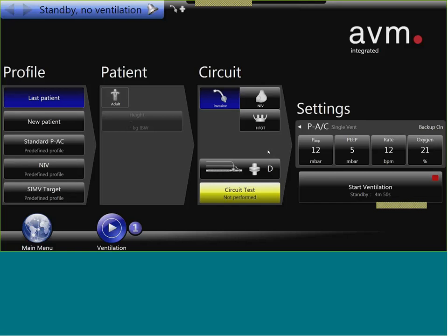Because it's for HFOT, it's on purpose. We just want that there is no mix-up between oxygen therapy and non-invasive and invasive. There are other competitors out there which have HFOT in the same panel as any other ventilation mode, and we just thought there is no alarming at all. So if someone is starting the ventilation and unfortunately presses the HFOT button, there won't be an alarm to make people aware that this patient is not ventilated at the moment. So HFOT, we wanted to have it totally separated.